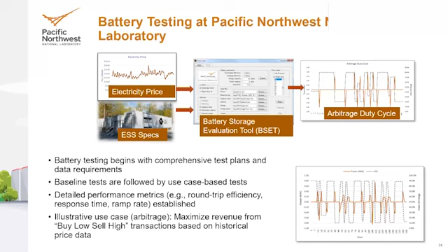Then we define a number of use cases. So what does arbitrage look like for this system at this location for this utility? We create a duty cycle for the energy storage system to follow for a 1-week period, the same thing with respect to frequency regulation. We try to make it as realistic as possible. We run through all those use cases back through the DOE OE test protocol, and sometimes we'll perform tests interseasonally, cycling back through 2 or 3 times to yield as sophisticated and accurate results as we possibly can.